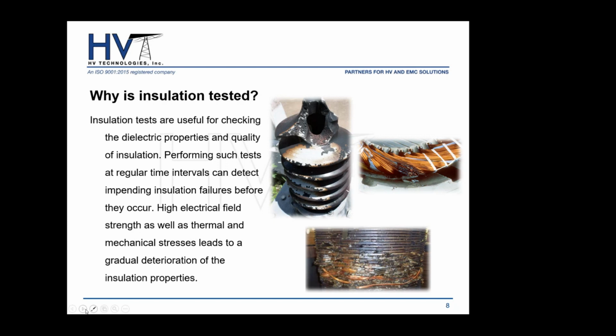Usually tests are done at the factory, and you may get a manufacturer's certificate saying these are the measurements that we took at the factory for tan delta and capacitance. Then once you perform these tests at regular intervals, you can start to trend and gauge any change in your capacitance or dissipation factor measurements. That's how you can determine whether your insulation is nearing impending failure, or if it's something that maybe you might want to replace or maintain.